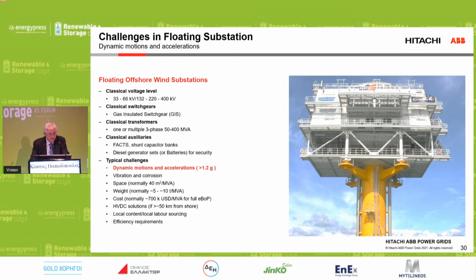Of course, rusting and corrosion is another problem. The space — you need about 40 square meters per MVA — and the weight, you need to handle about 5 to 10 tons per MVA. The cost, about 700,000 dollars per MVA. That's a typical cost.